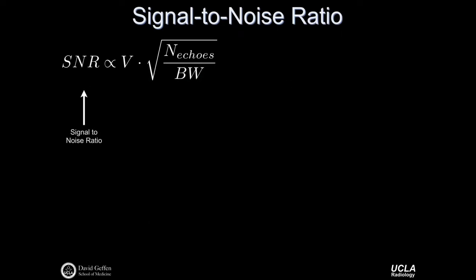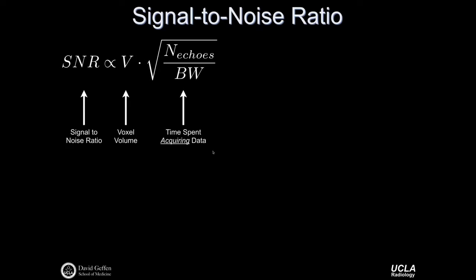The signal-to-noise ratio is also directly related to acquisition parameters we control. The SNR is proportional to the voxel volume — the volume of tissue contained in a pixel. Larger voxel volumes give more signal-to-noise, but also lower spatial resolution. The second part of this expression relates to the time spent acquiring data: the square root of the number of echoes is proportional to SNR. To double your signal-to-noise, you would have to acquire four times as many echoes, which can be quite costly in terms of time.